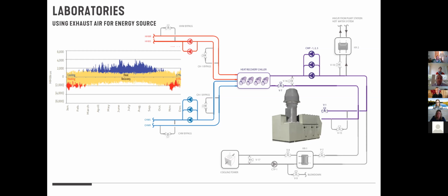So in addition, a lot of these projects use a system called VAV with reheat to modulate air and deal with pressurization between labs and non-labs. That system, by default, tends to result in a lot of what we call simultaneous heating cooling. So we're heating and cooling things at the same time. Traditionally, we've had a boiler that was heating things, and we have a chiller and cooling towers that are cooling things. And you're doing both of those things at the same time.